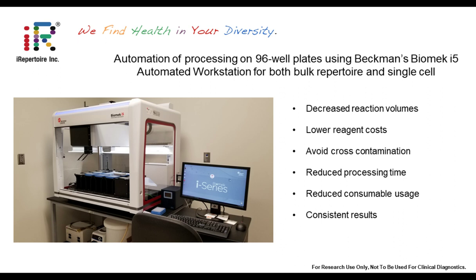The video showed some of the functionalities of the i5 robot. The robot was capable of low-volume transfer, and we were able to mix the beads with the PCR products very efficiently. One important feature is that we can reuse the 96-well tips, reducing consumable costs — using a tween wash and returning them to their original slots, cutting down from needing 10 boxes of tips manually to just one box. The gripper arm was also notable because it can pick up non-skirted plates, which we like because they're divisible, allowing us to score and test a portion of the plate before processing the entire plate.